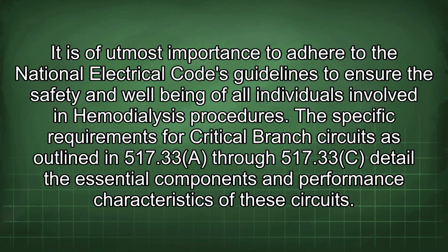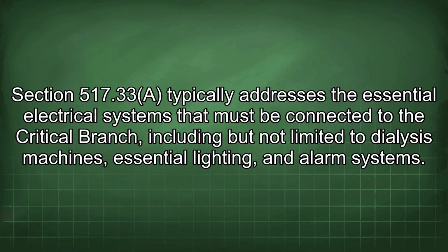The specific requirements for critical branch circuits as outlined in 517.33(A) through 517.33(C) detail the essential components and performance characteristics of these circuits. Section 517.33(A) typically addresses the essential electrical systems that must be connected to the critical branch, including but not limited to dialysis machines, essential lighting, and alarm systems.